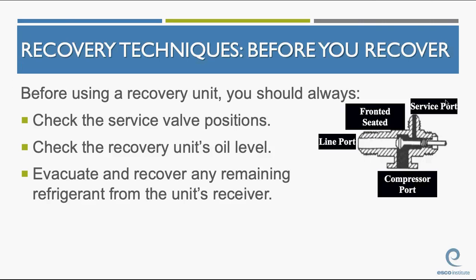Before using a recovery unit, we want to check the service valve positions. We want to check the recovery unit's oil level if needed. We want to evacuate and recover any remaining refrigerants from the unit receiver. Most of the newer systems don't have their own receiver in them. Again, we want to make sure we don't mix refrigerants, so make sure there's no refrigerant from another system left over in your recovery machine.